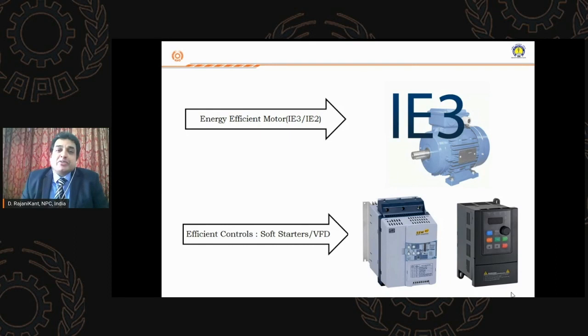Otherwise, an interesting thing as far as motors are concerned: in an SME, once a motor burns out, they send it for rewinding. That's a normal practice. If you send a motor for rewinding, the efficiency drops, and these are pretty old motors. But nowadays you have IE3 and IE2 motors. Depending upon the size and frame of the motor, you get as high as 96% efficiency. So it is suggested for SMEs not to go for rewinding so frequently. The same motor should not go for rewinding, as that will lead to more losses.